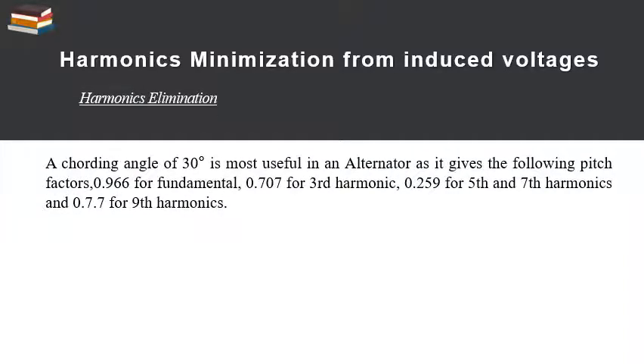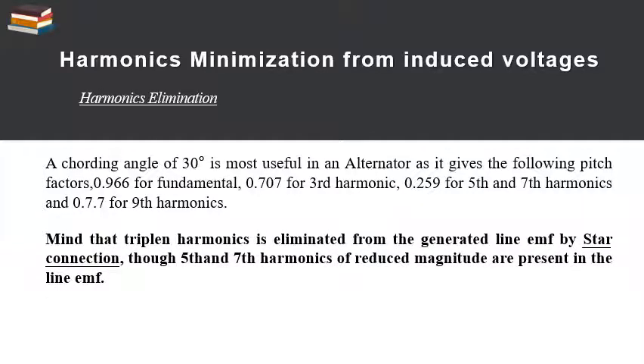A chording angle of 30 degrees is most useful in an alternator as it gives the following pitch factors: 0.966 for the fundamental, 0.707 for the third harmonic, 0.259 for the fifth and seventh harmonics, and 0.707 for the ninth harmonic. Mind that triplen harmonics are eliminated from the generated line EMF by star connection, though fifth and seventh harmonics of reduced magnitude are present in the line EMF.